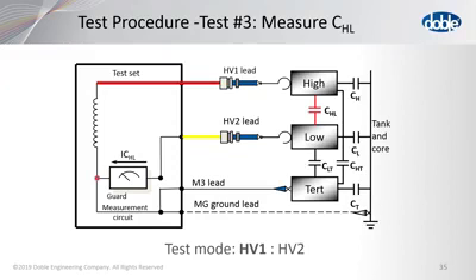In another situation, you may use that tertiary winding for substation power, where the high and the low are the main circuits, but the tertiary is for some substation power, for auxiliary power. Now, the tertiary in a three-winding transformer shouldn't be confused with a tertiary for an auto transformer. A tertiary on an auto transformer is used to make sure that zero sequence currents and such are taken care of. But in a three-winding transformer, it's a little different situation. That is not there for stabilizing. It's more for operational reasons.